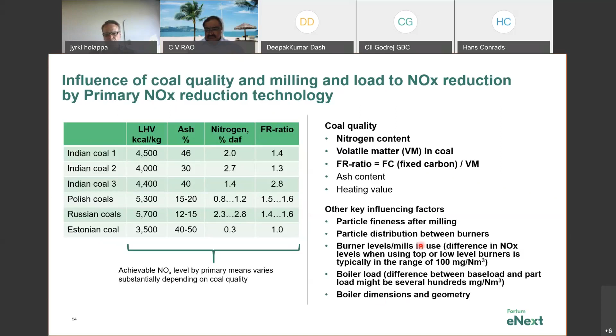The other key issues, also mentioned by Promecon, you need to be aware of: milling operations and air and coal distribution to your boiler, and which burner level mills are in use. These have a surprisingly big influence on NOx levels, and all these factors need to be considered when specifying and deciding what technology fits your plant.